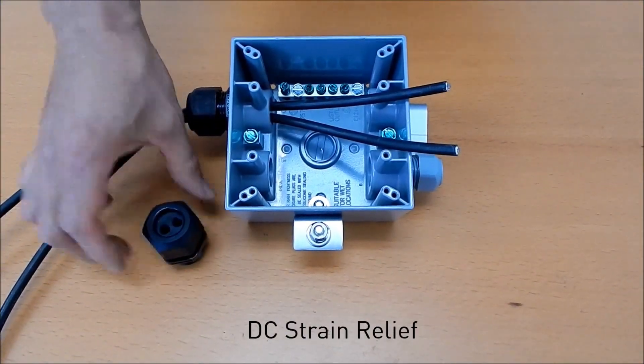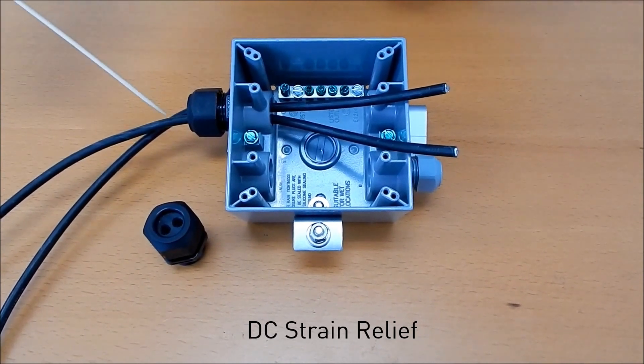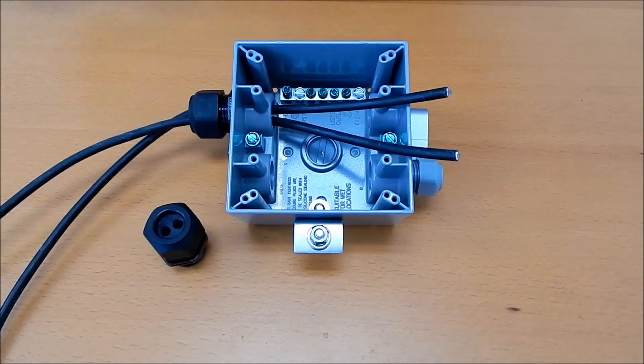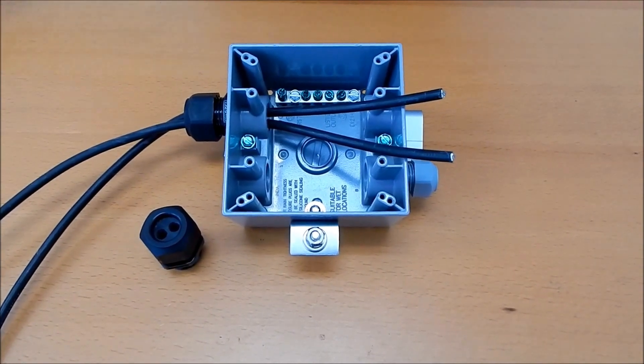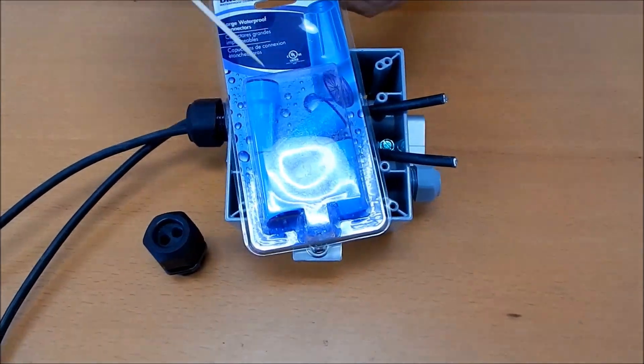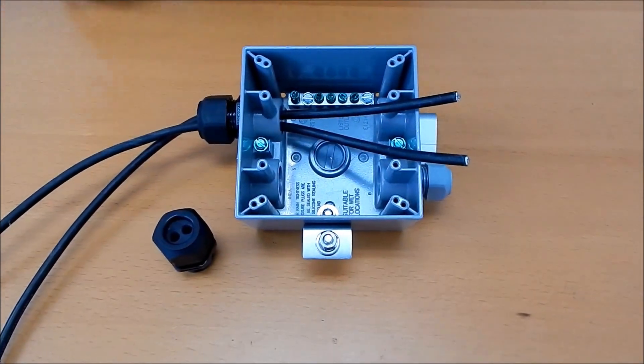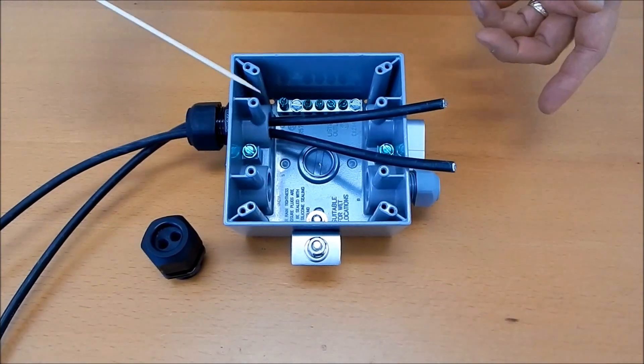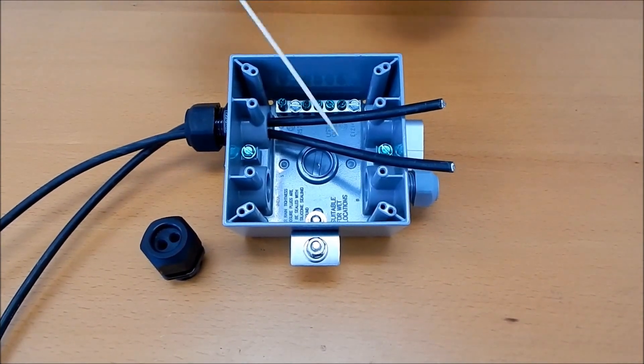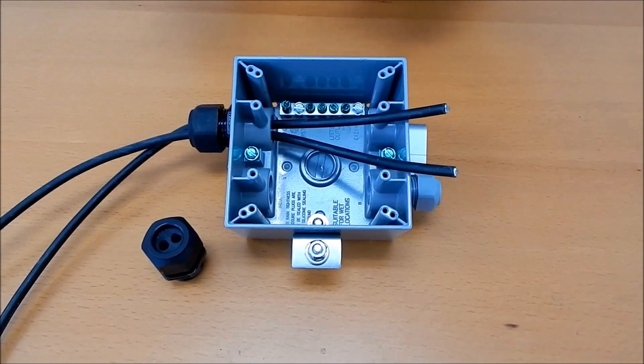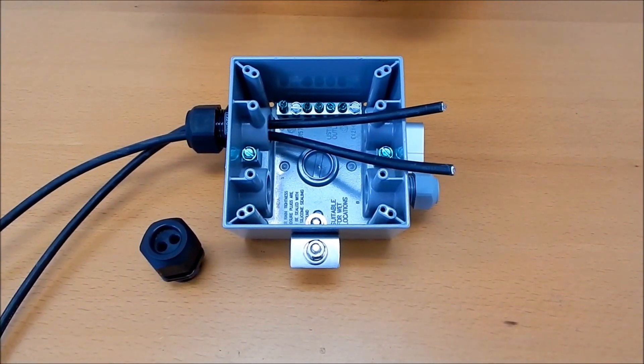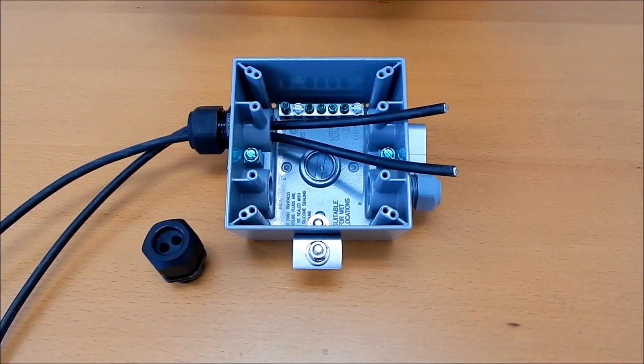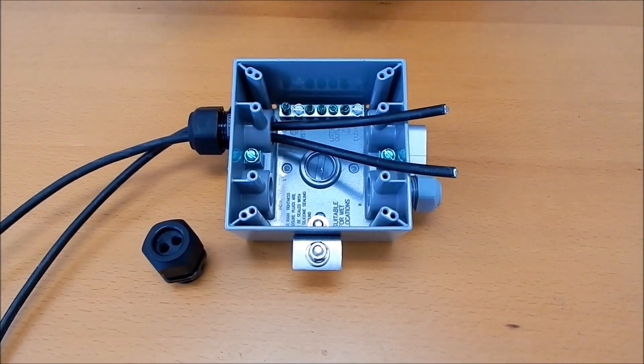Using the two-hole strain relief, you're able to put the PV cable through, which is about seven millimeters, so it's actually pretty large. And then what you want to do is transition to the THWN-2 wire, and using the wire nuts, you can get that going. And then what you also want to do is you'll have a bunch of black wires. You want to be able to do your housekeeping. So take the positive and label it with some red electrician's tape, and that way you're actually able to maintain the DC convention of the red is positive and the black is negative, just like in your car.